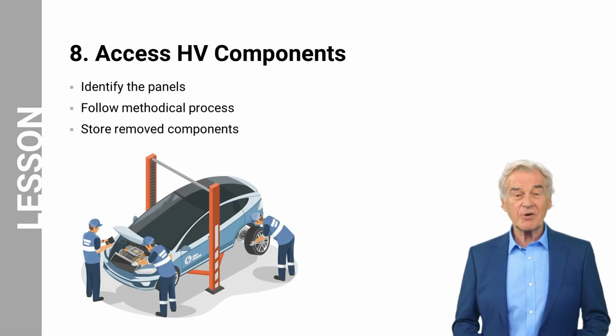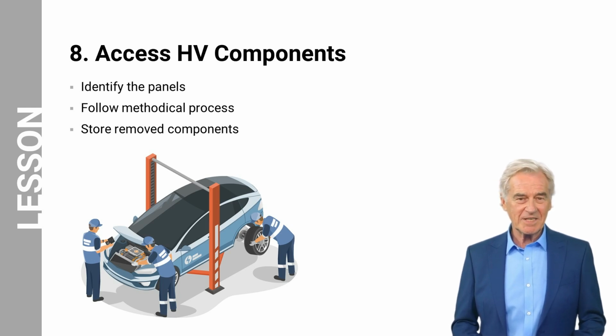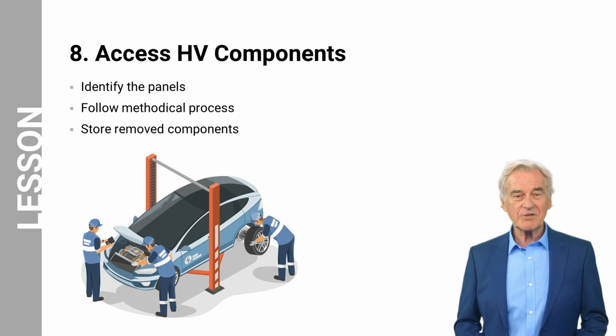Number 8 is access to high-voltage components. Consult the manufacturer's documentation, including service manuals and safety guidelines, to understand the procedures and precautions for accessing high-voltage components. Identify the panels or covers that need removal. Before removing any panels or covers, confirm that the high-voltage system is de-energized using a Cat3 digital multimeter. Follow a methodical process for removing panels or covers by checking the manufacturer's documentation. Once you have removed the necessary panels or covers, follow the manufacturer's guidelines for accessing the high-voltage components. This may involve additional steps, such as removing insulation barriers or protective covers. Store the removed panels or covers safely and securely within the work area. Keeping them organized ensures that they can be easily reinstalled later.